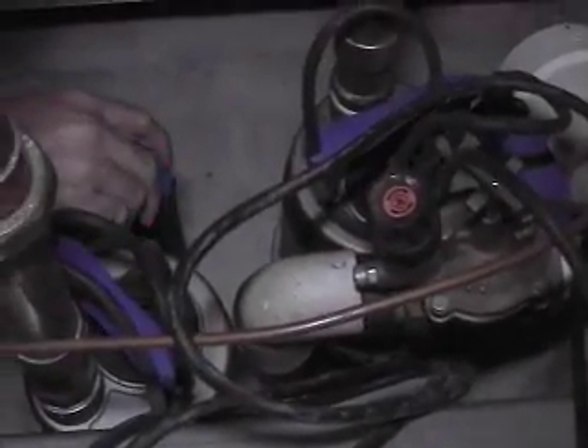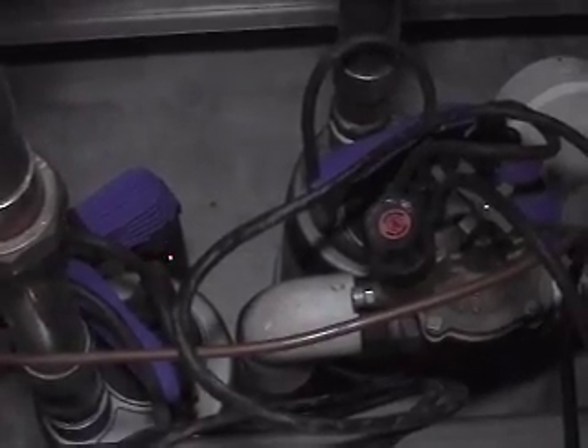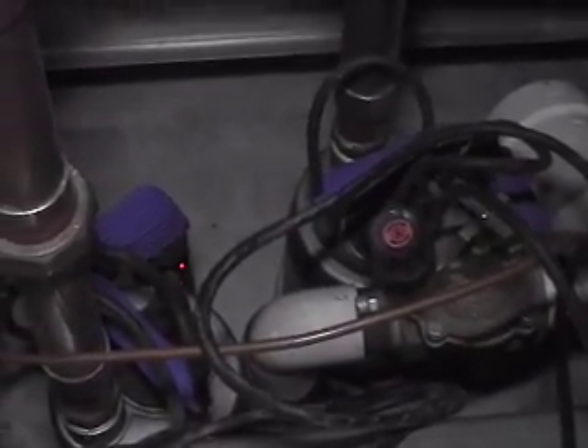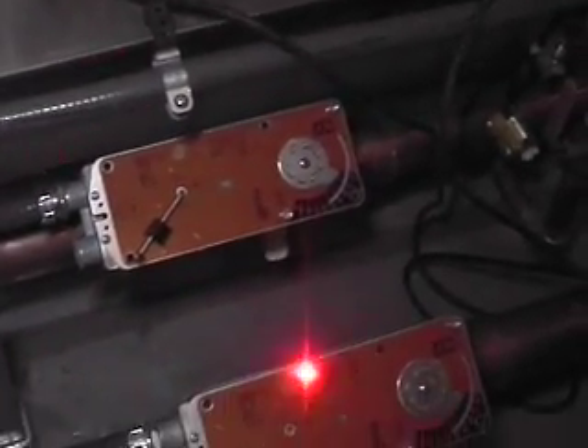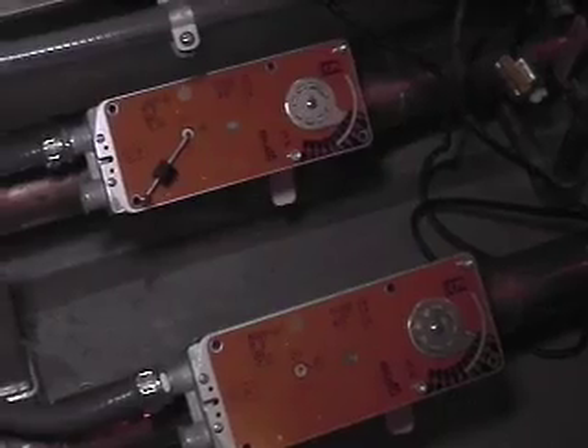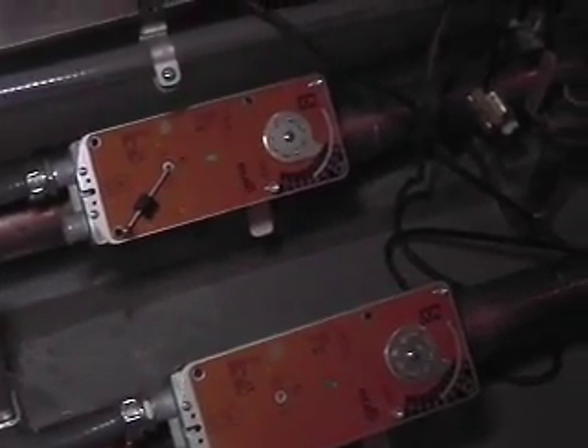These pumps here, you can see the floats on the outside here. So when the water level's high enough, that'll enable them to come on if our enable's turned on from the system. We monitor status. There's a CT on each one of these 4 pumps, and then they're wired in series. So if all 4 of them are running, then we'll show a status on the graphics. There's 2 drain valves here, one for each side. And this valve here is your wash valve.